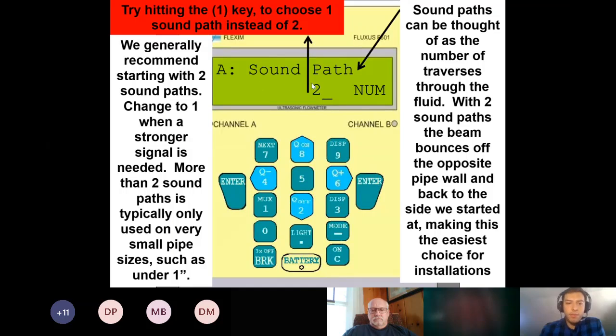And the sound path. So the sound path, we typically recommend folks starting with a 2 sound path. A 2 sound path is where the transducers are both on the same side of the pipe, and you mount the transducers, so the ultrasonic beam bounces off the back end of the pipe and then hits your other transducer. So any even number sound paths, the transducers are going to be on the same side of the pipe, and then any odd number sound paths that you choose, the transducers will be in a direct mount on opposite sides of the pipe.